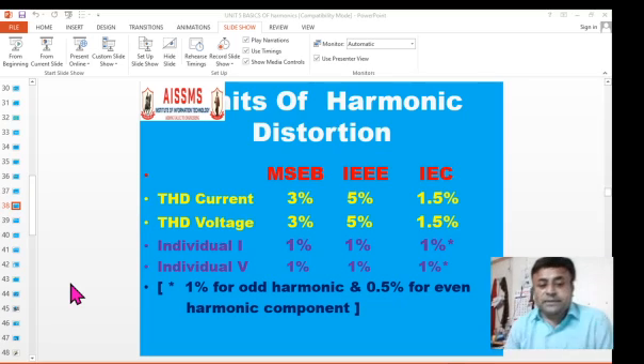Coming to voltage harmonic distortion level, for the MSEB standard it is 3%, as per IEEE it is 5%, and as per IEC it is 1.5%. So in general, the IEEE standard of 5% is taken into consideration as a permissible limit for voltage distortion. Then coming to individual distortion, there is 1% in all the cases.